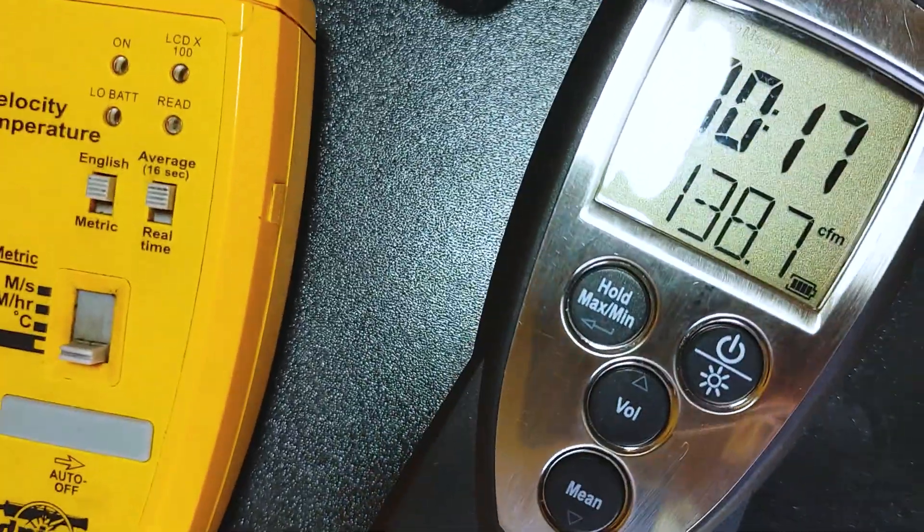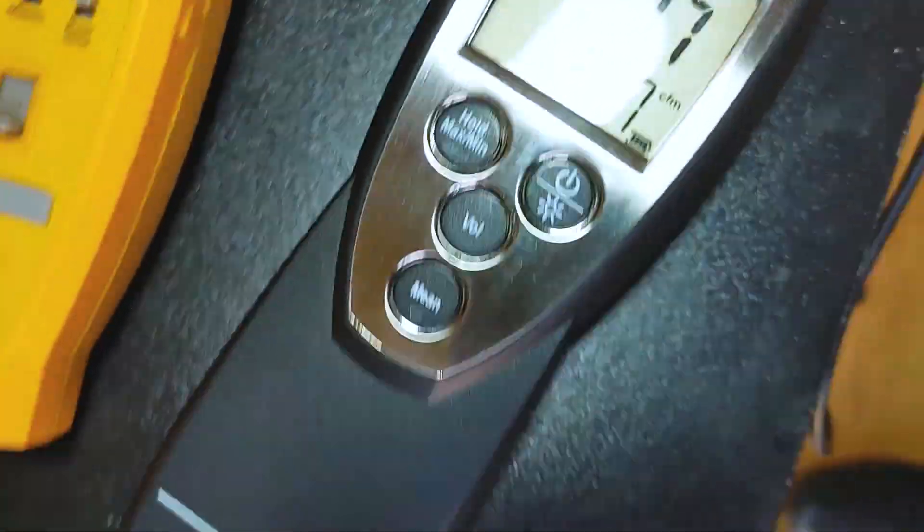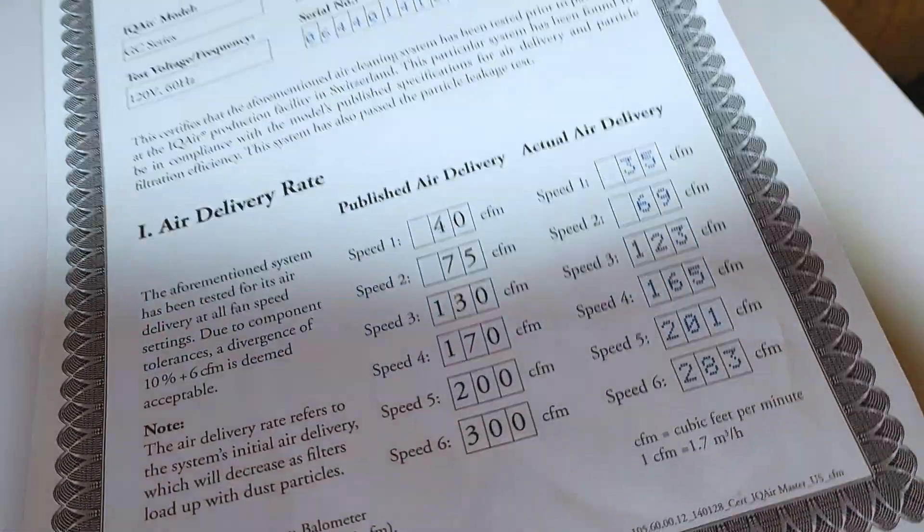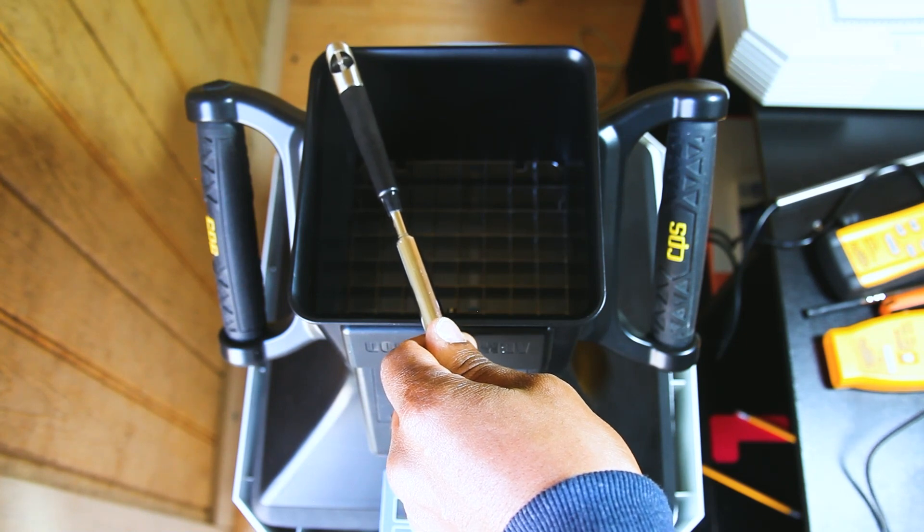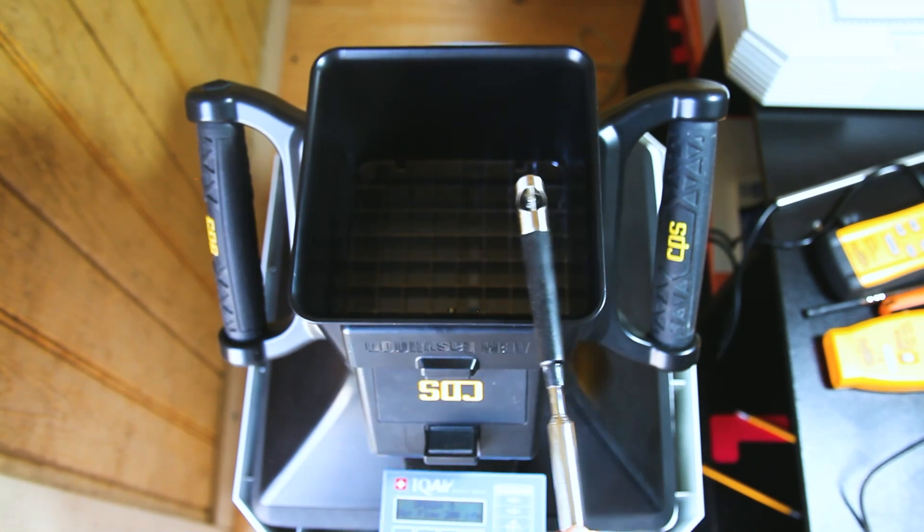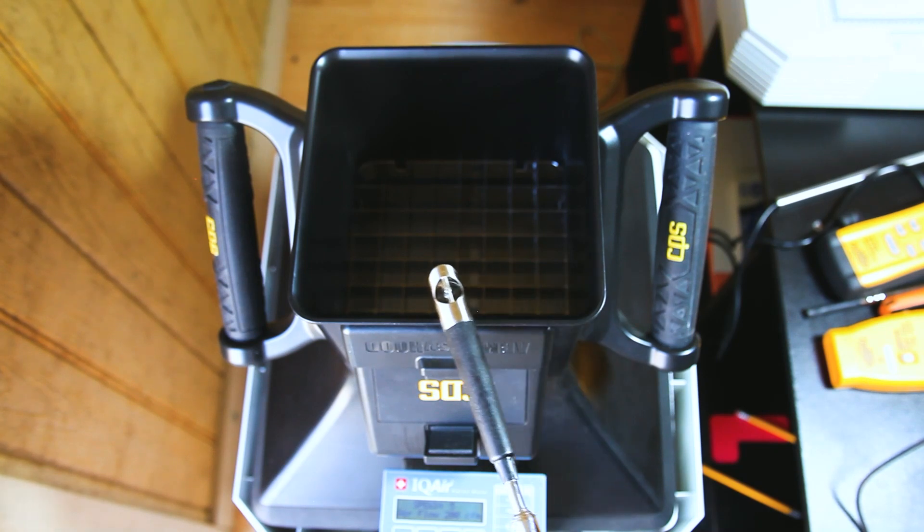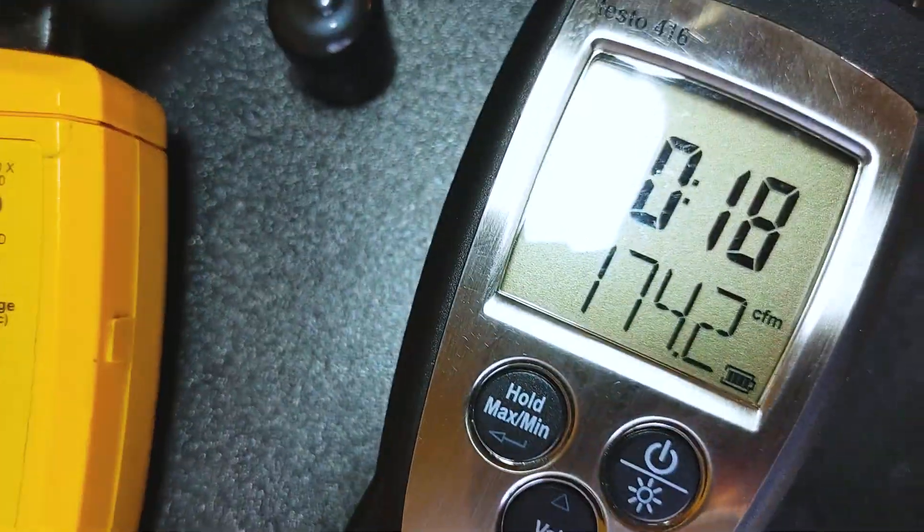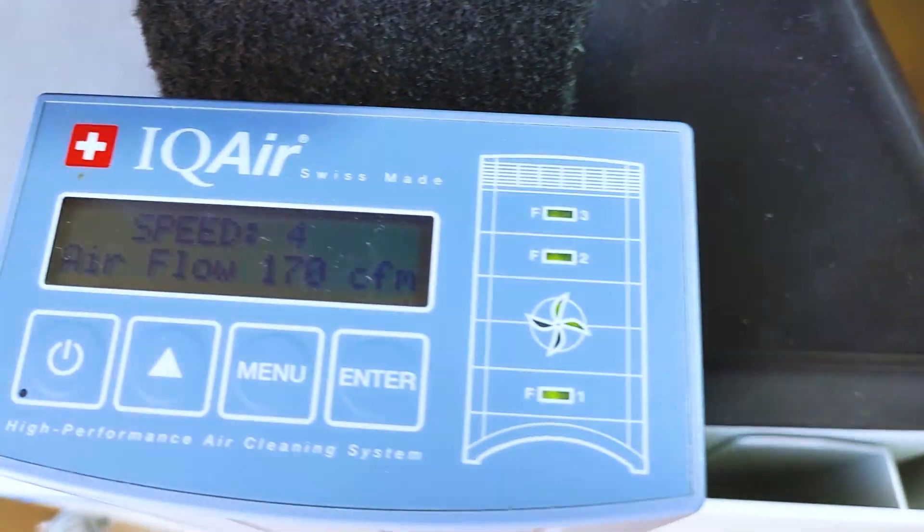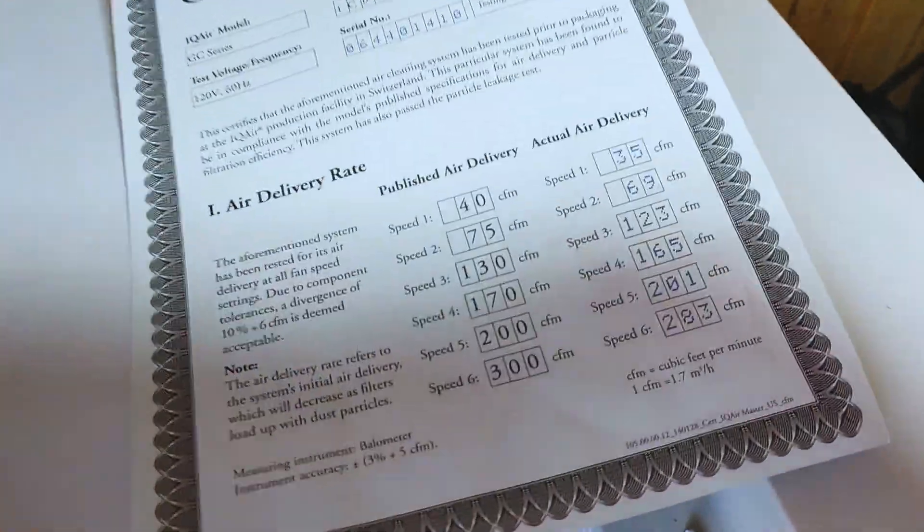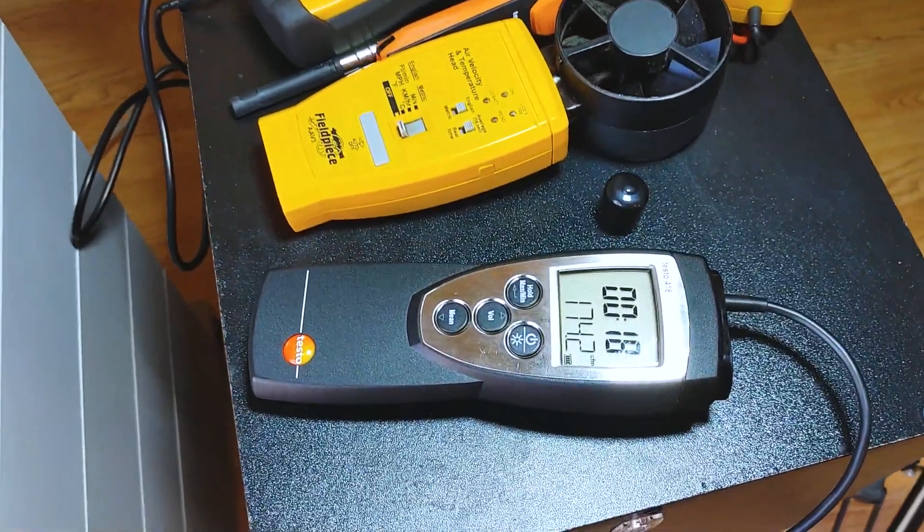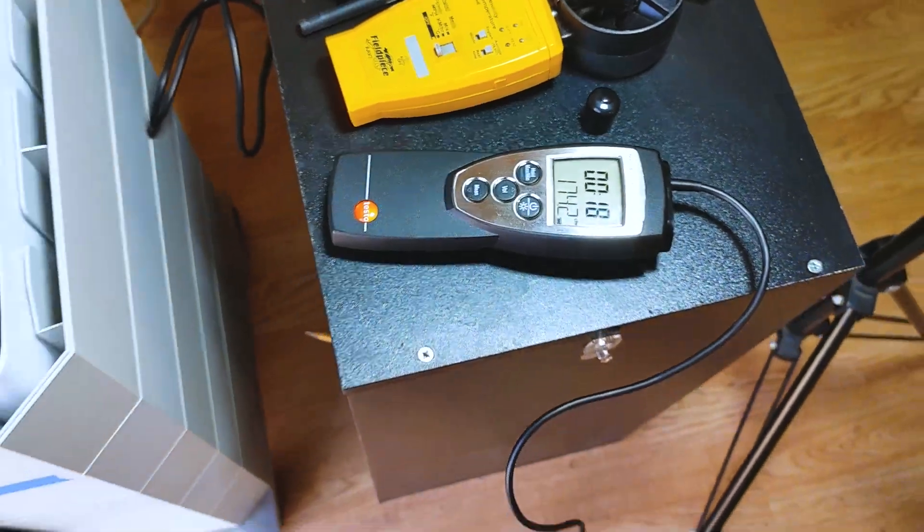138 on speed three, should be 130 design, and the manufacturer got 123. 174 on speed four, design 170, manufacturer got 165. So as you can see, this 416 is reading consistently high. Let's keep it up.